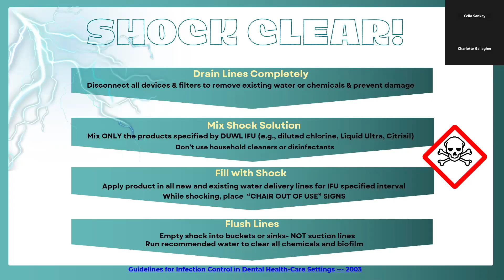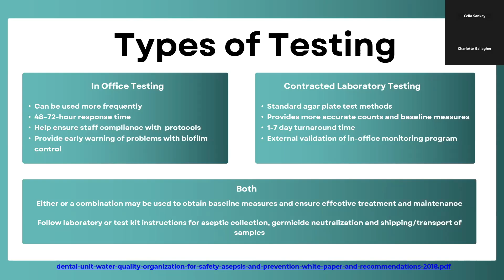In-office testing, which can be done more frequently, has a 48 to 72-hour result time. It may be used to verify compliance, a shock treatment's effectiveness, or provide an early warning of biofilm problems. Alternatively, you may choose a contracted lab service, which has a 1 to 7 day turnaround time. Off-site labs can provide more specific baseline data via agar plate methods. Labs may be used as an external validation to your in-office testing, treatment, or maintenance. Either way, carefully follow the test instructions for aseptic collection, germicide neutralization, and transport of samples to ensure testing accuracy.